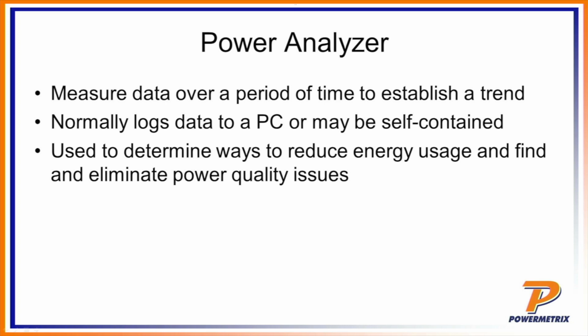A lot of times that can be done with a PC. For example, you can take a laptop out with a power analyzer module that plugs in. More modern power analyzers are self-contained, meaning that they have basically memory inside of them, and so they can be taken out to remote sites and plugged in and record that data for long periods of time. It used to be that you'd have to go out and install it and record that data for a long period of time and then go back out to the site and take it out.